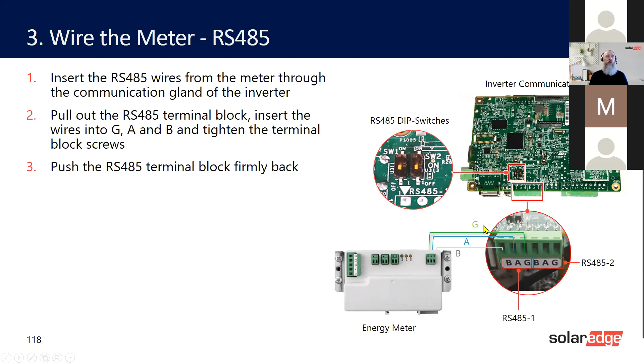So, meter configuration. You know how to get onto the inverter: you scan the QR code, connect to it, and then you can go into commissioning. You've got site communication, then RS485-1, then RS485-2, then set up the protocol. Remember, this is a meter, so we want to go to Modbus multi-devices. Why Modbus multi-devices? Because it allows multiple devices, so you can put the battery on there. You can have 3 different meters, meter 1, meter 2, meter 3, and you can have battery 1, battery 2, okay?